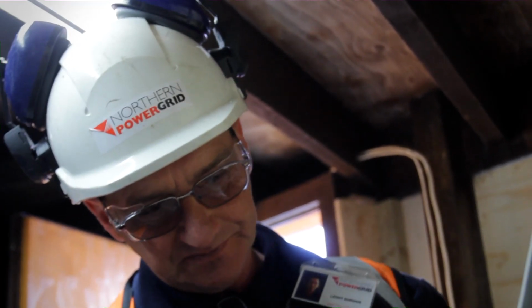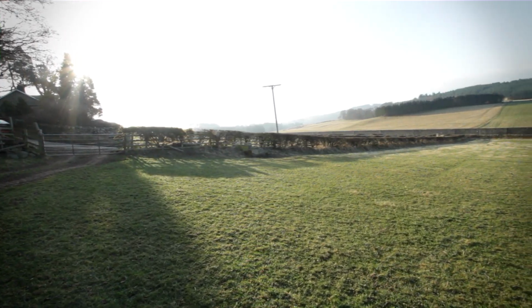The CLNR project is about connection of renewable and low-carbon generation, and it's also about getting the most out of your assets as a distribution network operator. It could change the dynamic of how people are connected at present, seeing whether we can offer them a different type of connection agreement, in relation to the capacity of the line and how environmental conditions can change that capacity. They could be on a rural network with a small capacity line, but we may be able to connect them with the use of thermal rating equipment and give them that connection capacity.